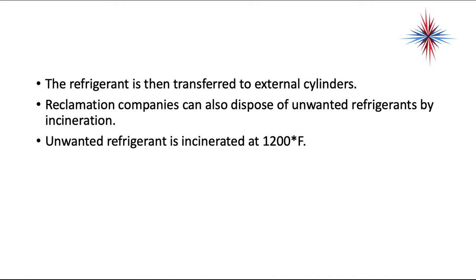Reclamation companies can also dispose of unwanted refrigerants by incineration. Unwanted refrigerant is incinerated at 1200 degrees Fahrenheit. That burns the chlorine in them.